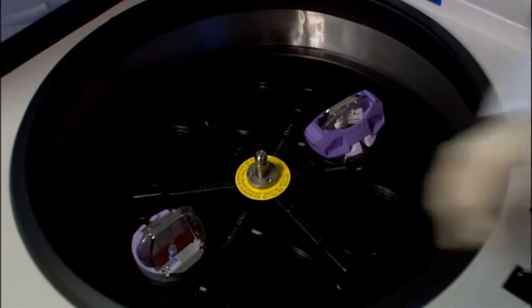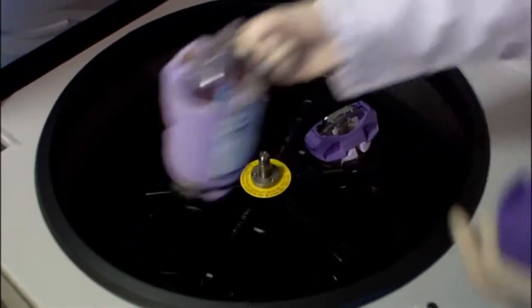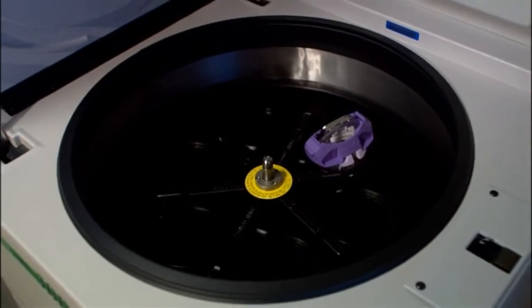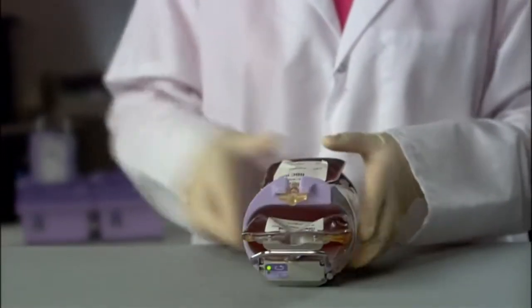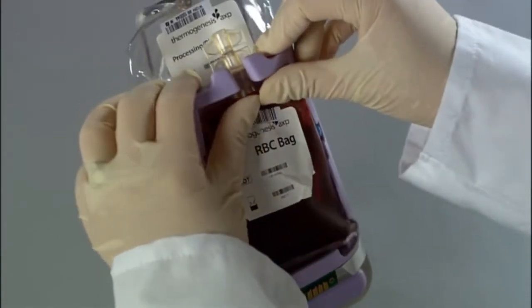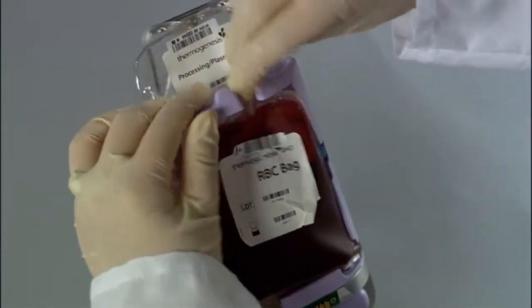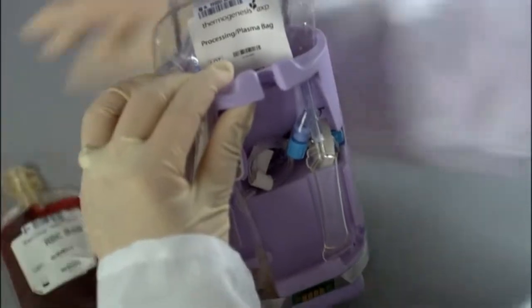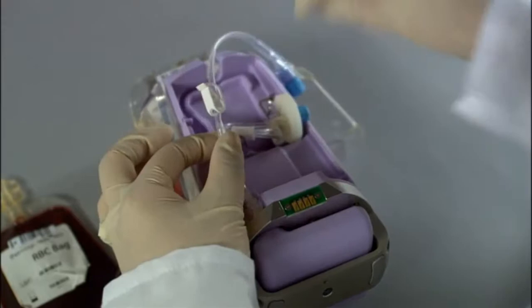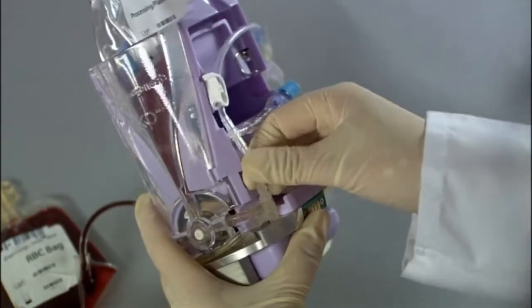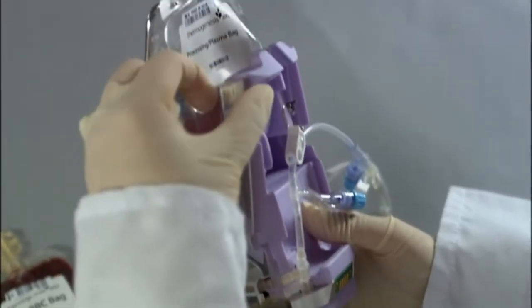Remove the weight compensation cap from the device before taking the device from the centrifuge. A green cycle LED on the device will indicate that the run has been successfully completed. Remove the processing set from the device, starting with the RBC bag, sampling segment 2, and the DMSO line. Next, unhook the processing bag and release the F fitting from the groove.